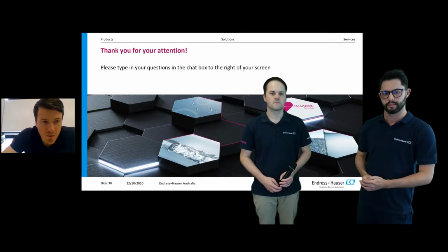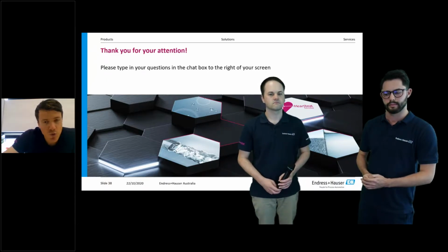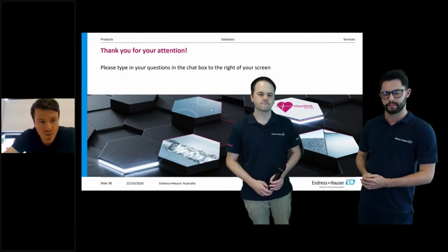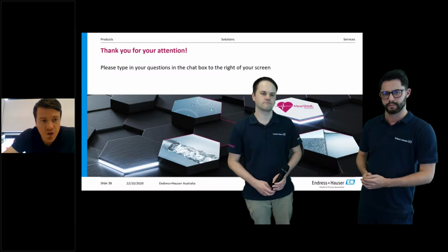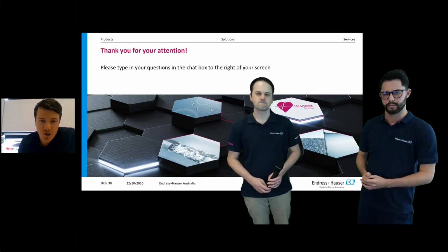We've got a really good question from Ed as well. Ed's asking, why is there no statement in the certificate about the percentage accuracy? The field check, which is our previous type of verification for flow meters, has a statement of the percentage deviation from the original factory data. Ed, that's not possible with heartbeat verification. It is an advanced type of verification procedure.